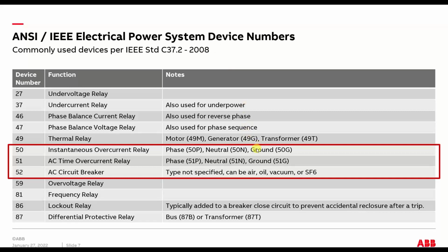And these are not only valid for the circuit breaker, switchgear world, but also the control. So if you're designing a motor control center schematic, you would use the same device numbers. So they're sort of universally used in the power control realm of engineering. Here's a very abbreviated list. The total list is this IEEE standard, and we have our own. I know ABB has a couple really nice printouts of descriptions of all the device numbers and what they do. If you shoot me an email, I can send you a copy of that.